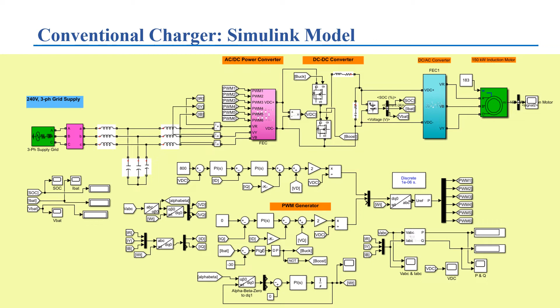The simulation plots for voltage and current delivered to the grid from the vehicle are shown on this slide. As can be observed, the desired sine wave voltages and currents are present. The individual phase voltage is a little less than 200 volt peak, hence we can calculate that the phase-to-phase voltage achieved is 240 volt RMS as per grid specification, while the current value is around 29 amps RMS.